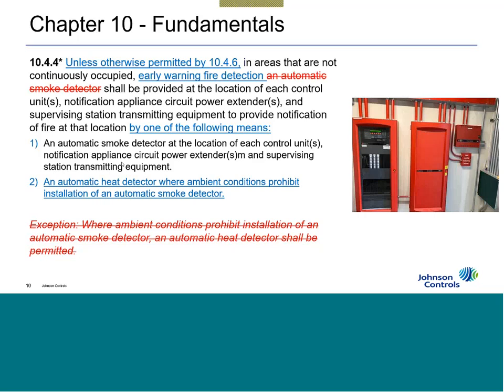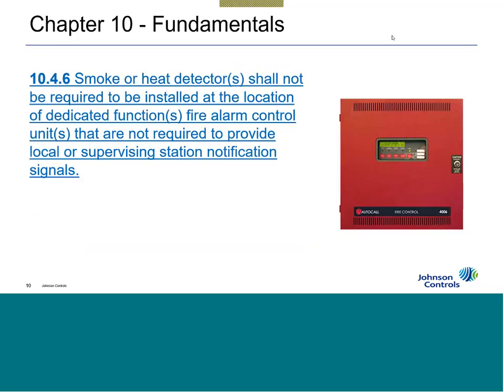And there's been a lot of debate. Well, what if I've got a sprinkler head in that same room? That's fantastic. Doesn't matter. A sprinkler head helps to quench a fire or stifle a fire or perhaps put it out, but it's not made to be the early warning fire detector for a fire alarm system. There's been a lot of debate about that. And the sprinkler systems have that really nice, clean, great water that comes out of it, right? Not. It goes right into the top of the fire alarm panel. And what do we have up here that UL requires us to have? Little vents for the heat to escape. A great channel for that nice water to go right inside and take out the control unit. So whether there's a sprinkler head in there or not is irrelevant. The code requires it to be there if it's in an unoccupied area.